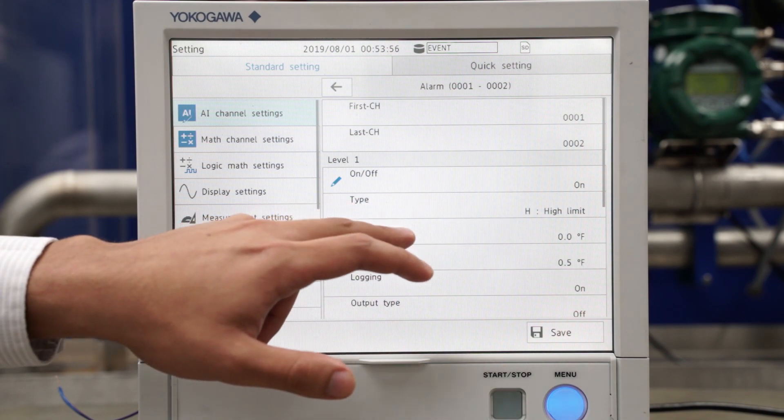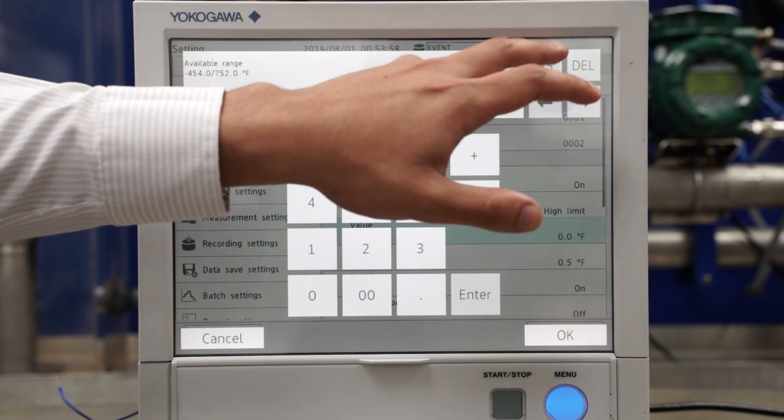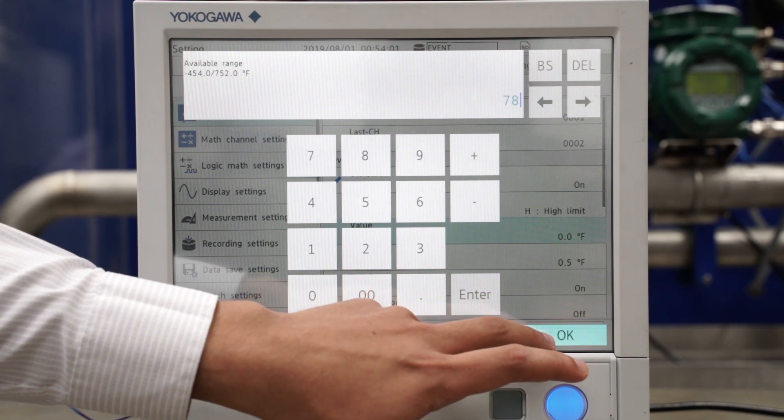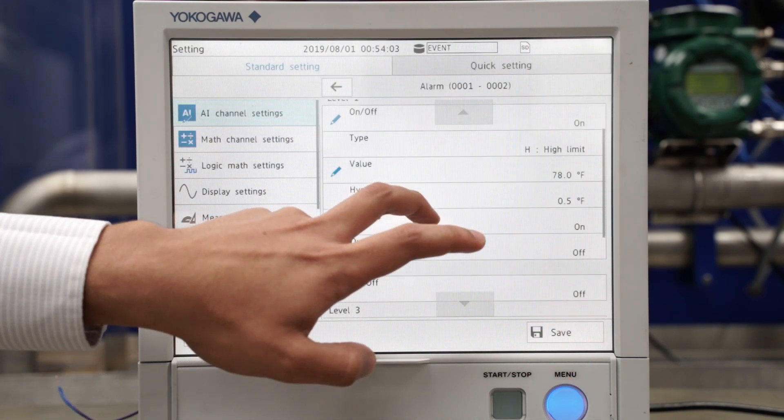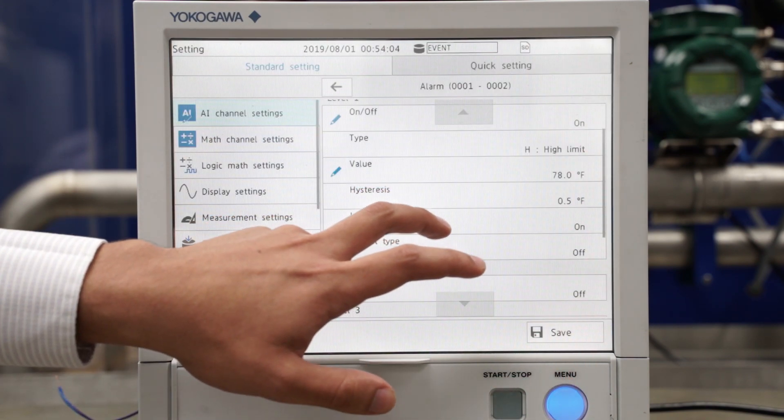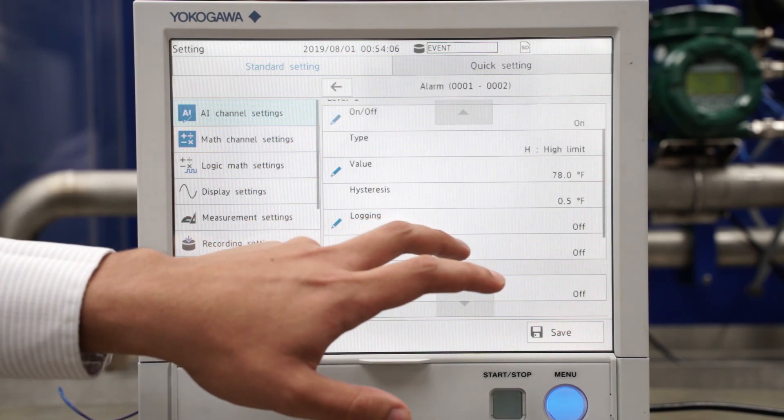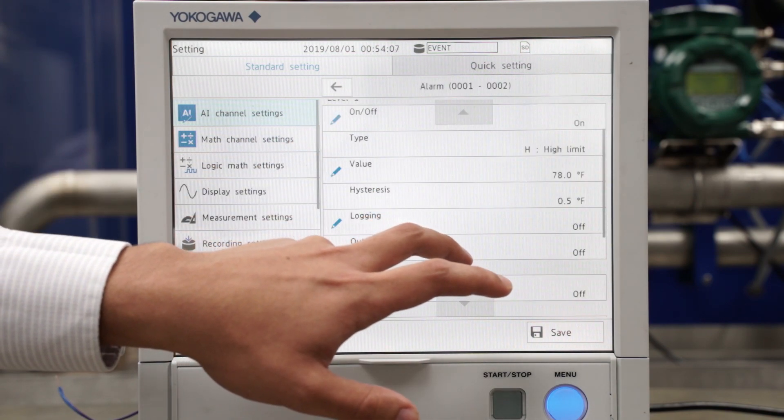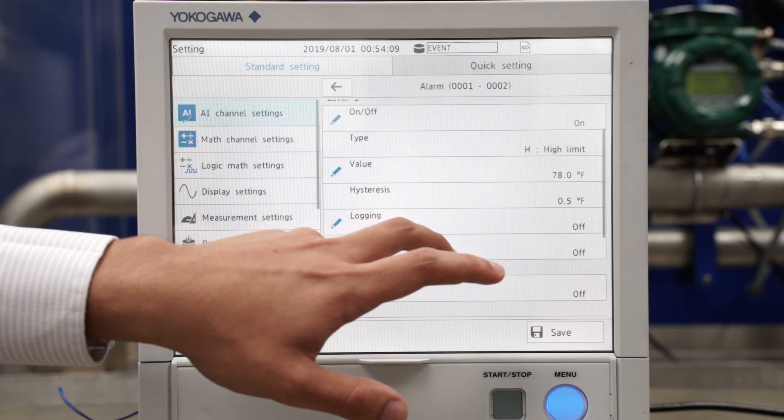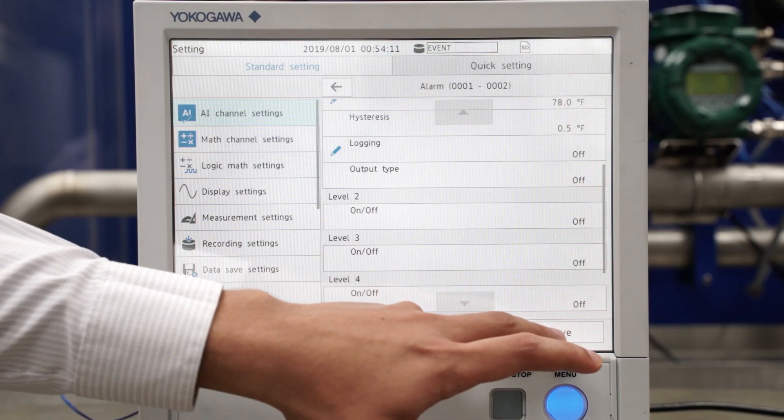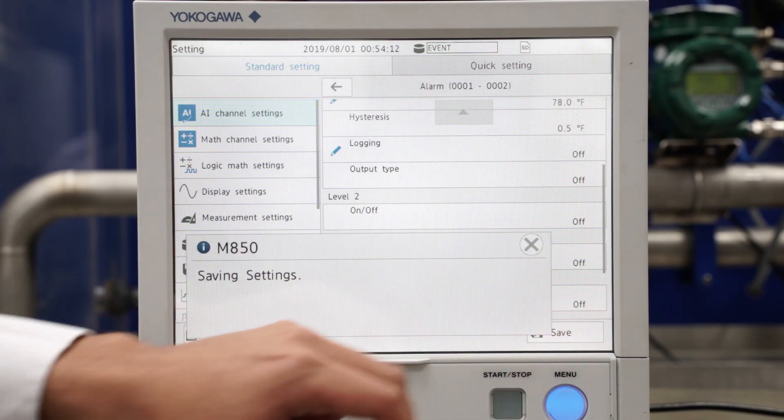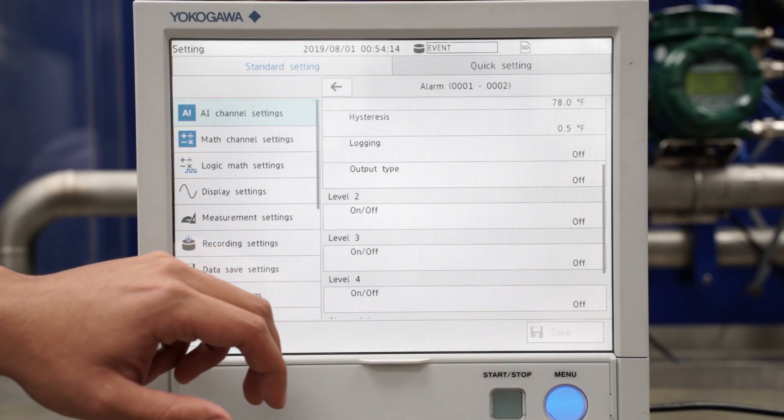High is the type of alarm. The value I said I wanted was 78 degrees Fahrenheit, and I don't want any logging because I don't want it to show me anything. I just want it to switch screens, and I'll go ahead and save that.